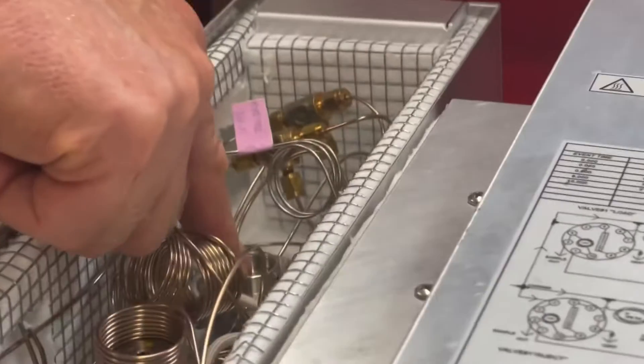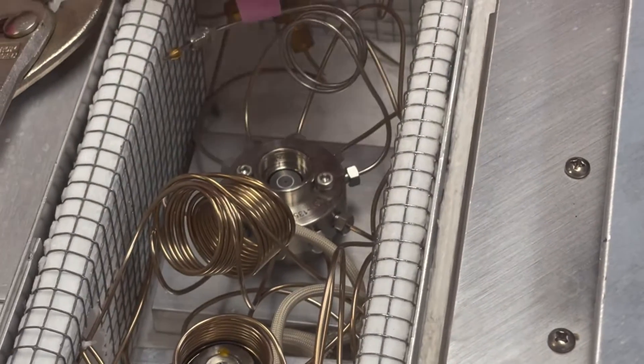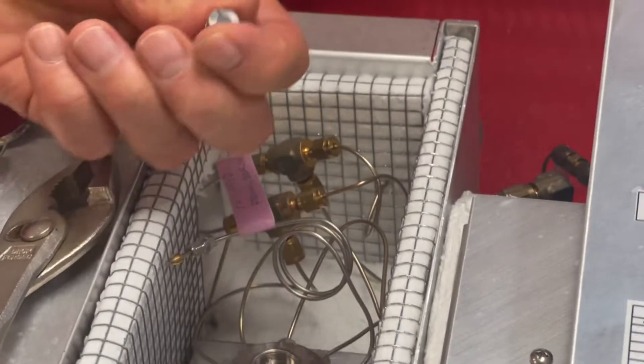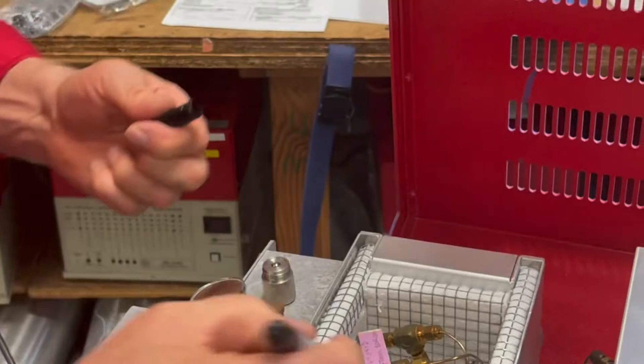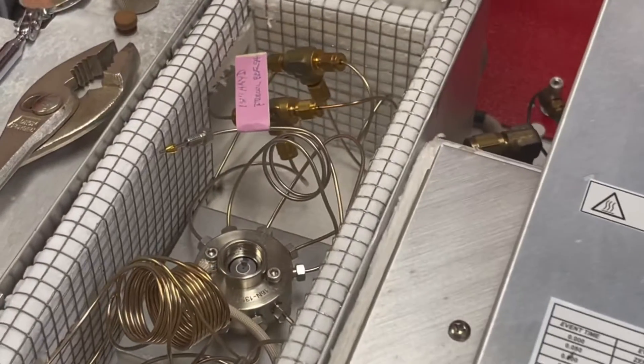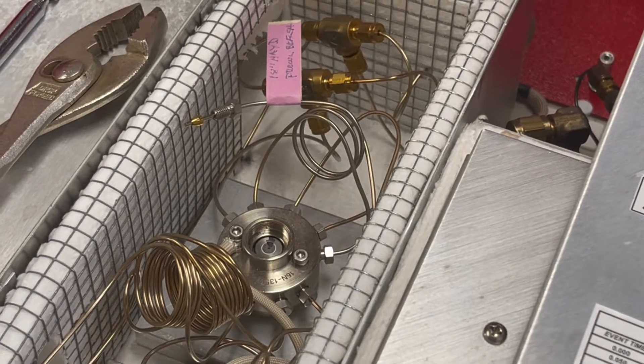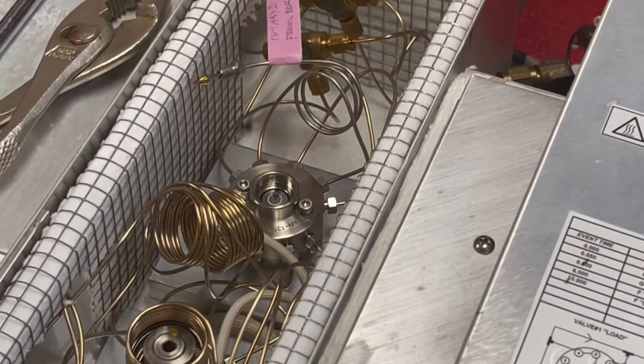Here's the rotor — it's down there in the valve, and it looks like this. You really can't tell which direction it was originally unless you take a Sharpie and put a mark on it. We usually put the mark toward the back side of the GC. It really doesn't matter as long as you can keep it straight, but that's what we do — put it toward the back side of the GC.